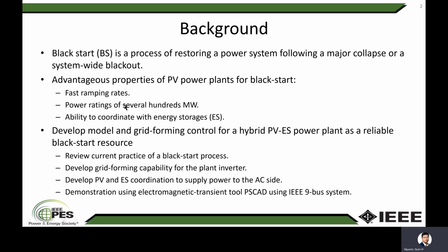they have power ratings of several hundreds of megawatts, and also they are able to coordinate with energy storage to increase the reliability. So in this work, we developed the model and grid forming control for hybrid PV energy storage power plant as a reliable black start resource. First, we review the current practice of a black start process. Second, we develop grid forming capability for the plant inverter. Third, we develop PV and energy storage coordination at the DC side to supply power to the AC side. Finally, we demonstrate the control and the black start process using electromagnetic transient tool PSCAD and IEEE nine-bus system.